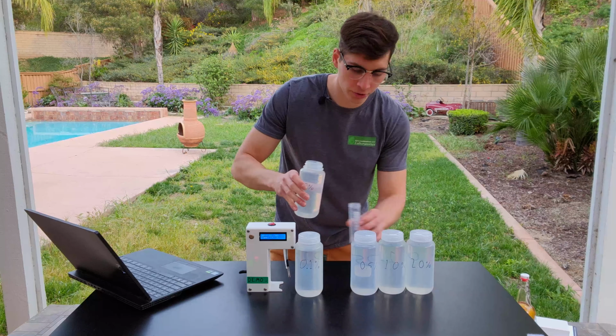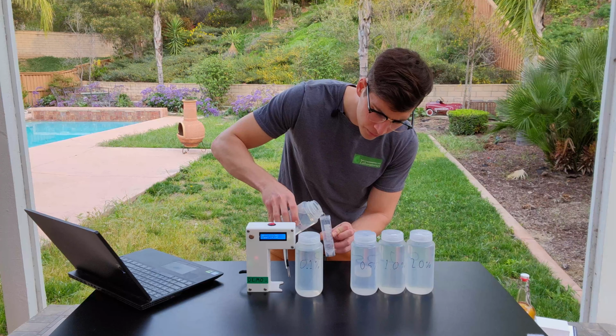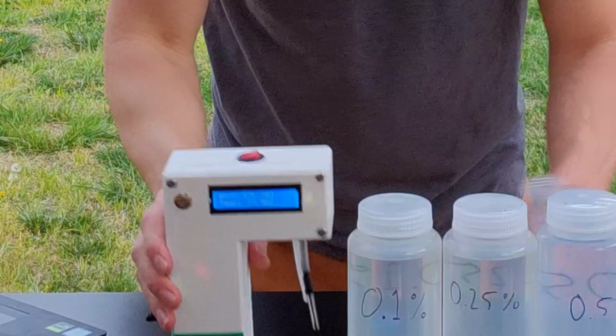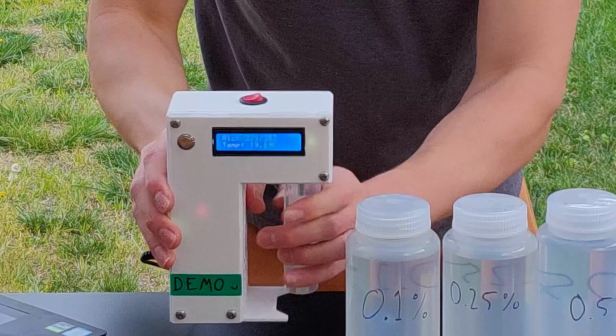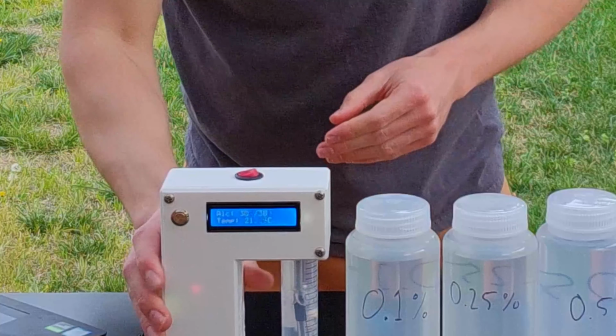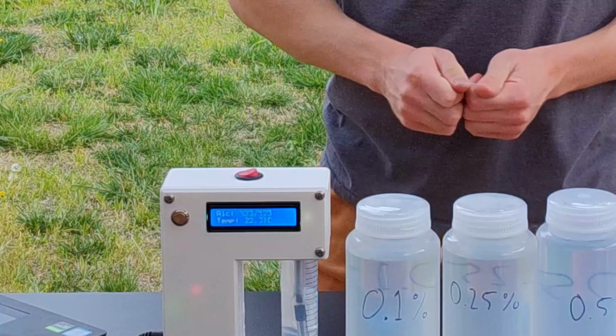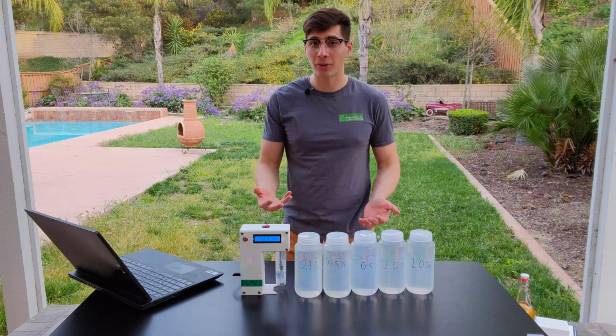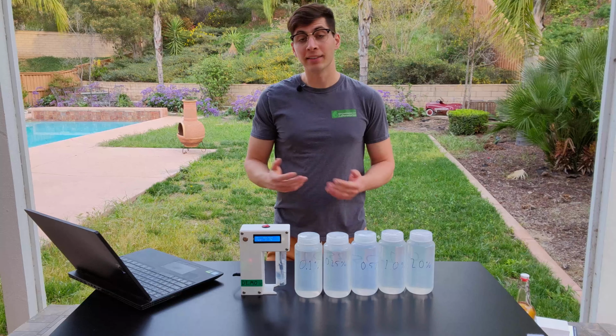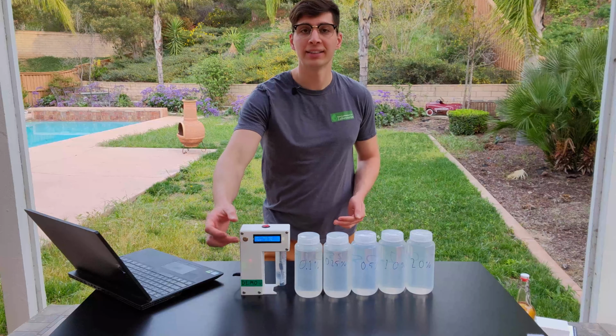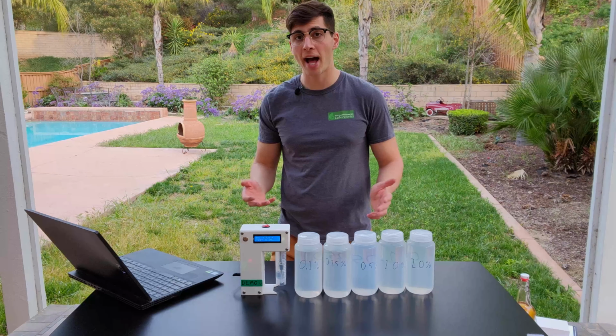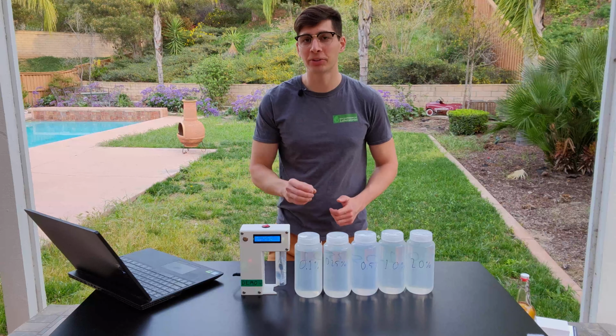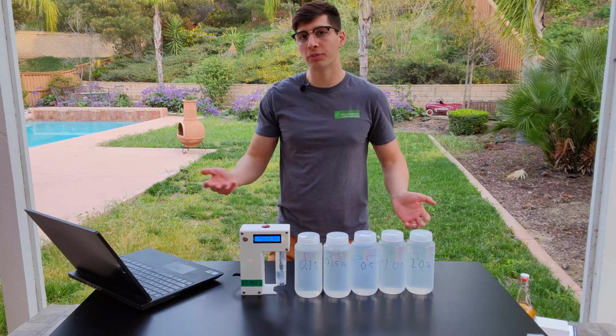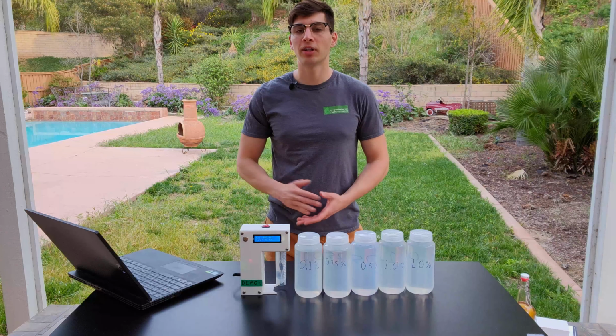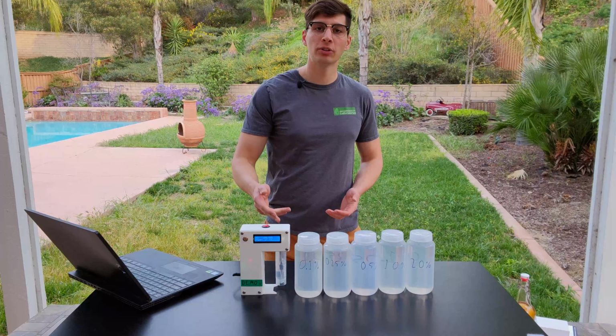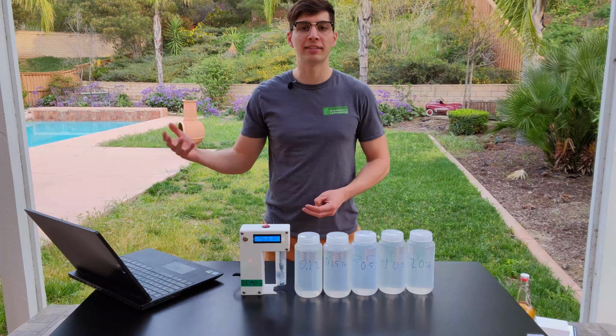So here is our 0.25%. I'll pour in about 25 milliliters again, screw it into the device, and you can watch as the readings climb. So this is a higher alcohol content, so we should get a higher reading. Now's a good time to also record the temperature that you're running your calibration curve at. This temperature will be your calibration temperature, and it will be the temperature that you measure all of your samples at. There may be some day-to-day fluctuations of your calibration temperature, but this temperature should be a target for measuring any samples in the future.